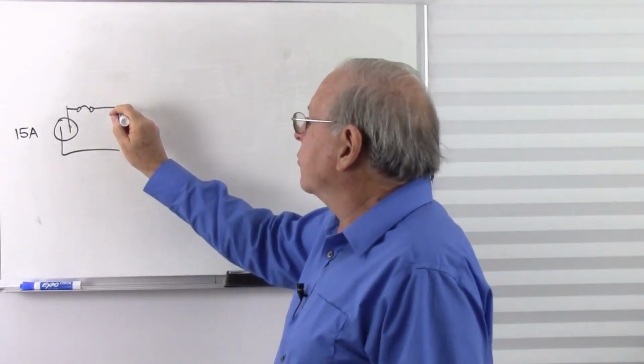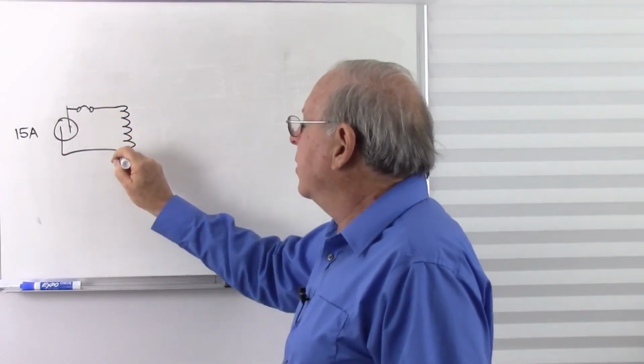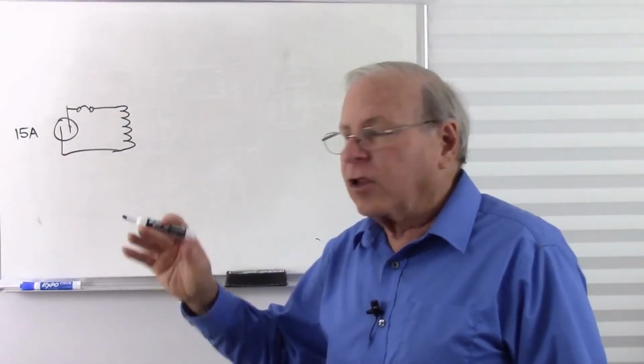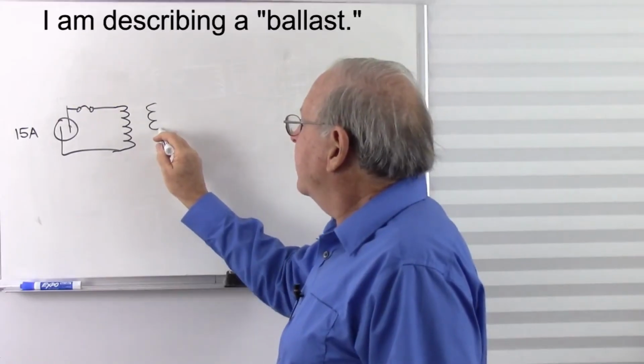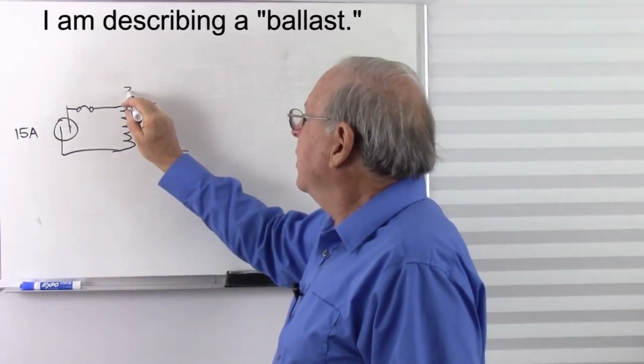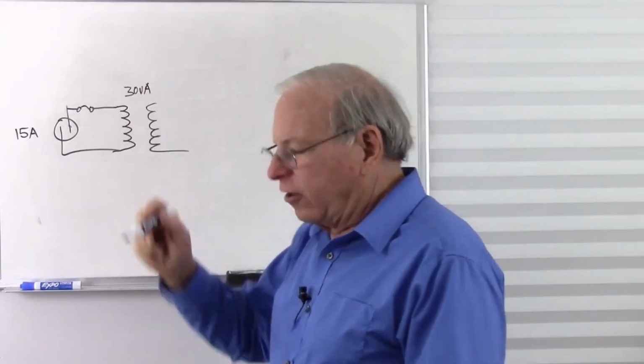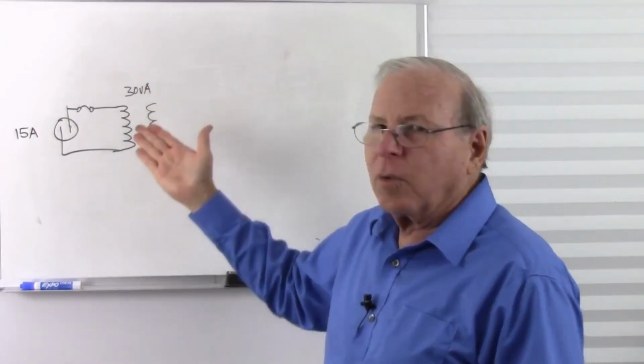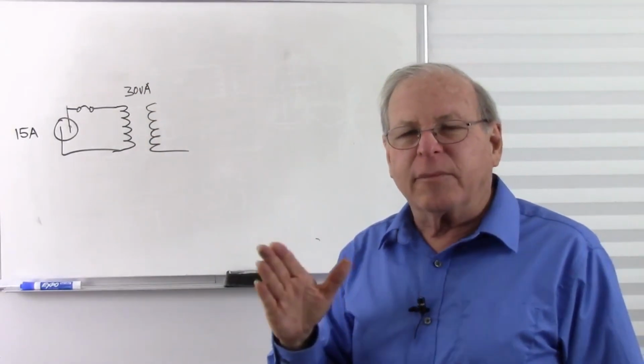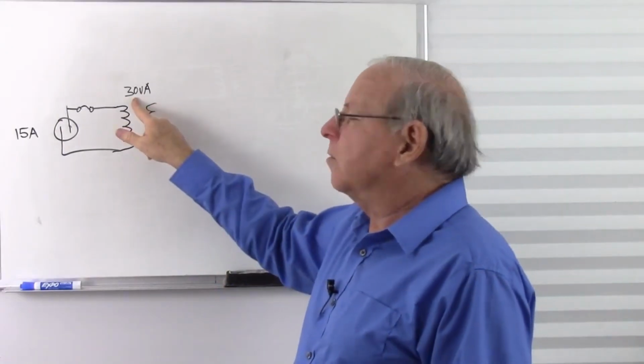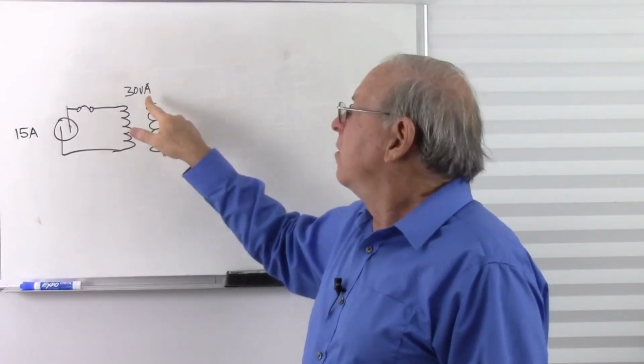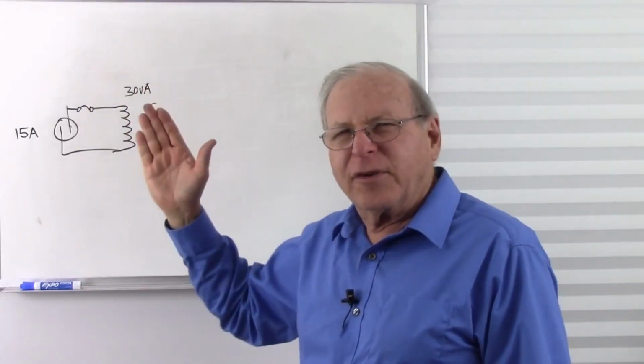So what can I do to mitigate that? One thing to do would be to use a small enough isolation transformer that it cannot pass a lot of current. So let's say about a 30 volt amp isolation transformer. Now this basically is 30 watts. Rarely you might see them rated in watts, but most often they rate them in volt amps. And what's a watt? Voltage times current. So this is a 30 watt transformer.